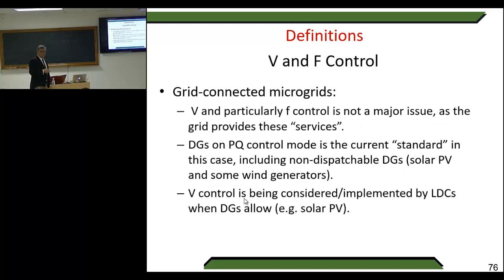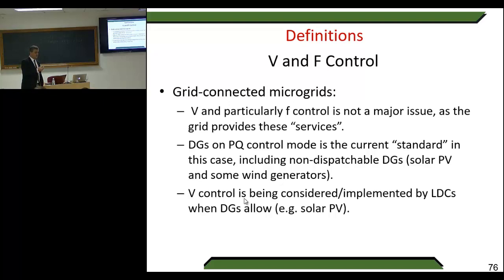We have grid-connected microgrids, which is one world, and islanding or off-grid operation of microgrids, which is normally for us the worst case. When analyzing a grid-connected microgrid in islanding mode, you need to be very careful — all what you learn from isolated microgrids is valid for connected microgrids when they operate in islanding mode. In grid-connected microgrids, voltage and particularly frequency control is not a major issue; they are provided mainly by the grid services.